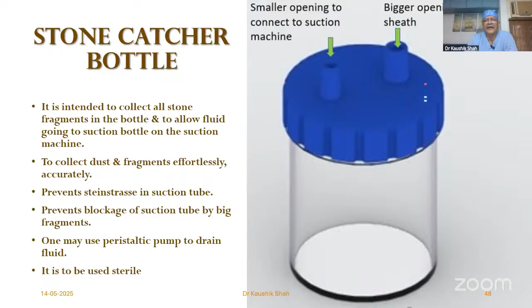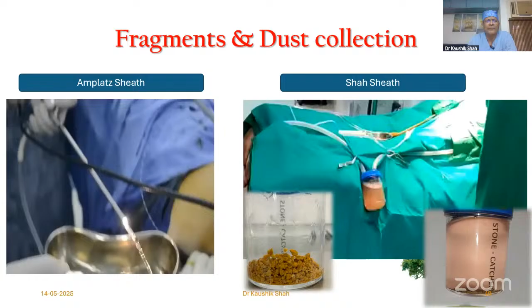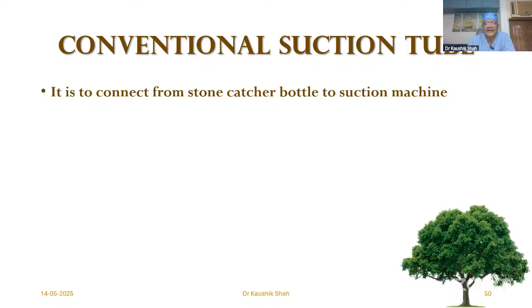So you can see here that you don't have to collect the fragments by putting in a kidney tray. It automatically gets connected, and you can collect all the dust, small particles, and everything. And you can use a conventional silicone tube to connect from the suction stone catcher bottle to the suction machine.